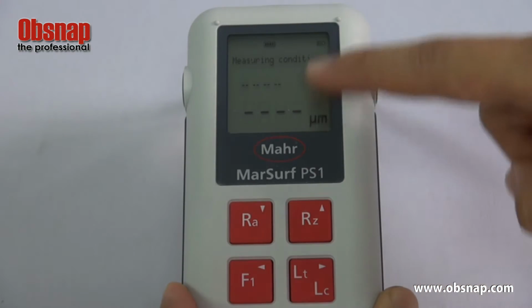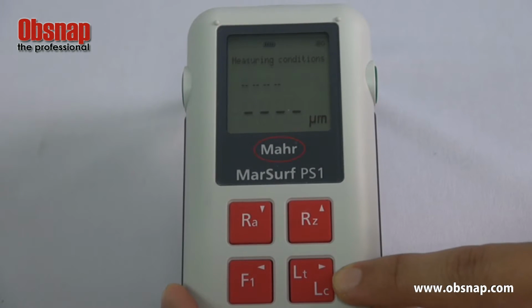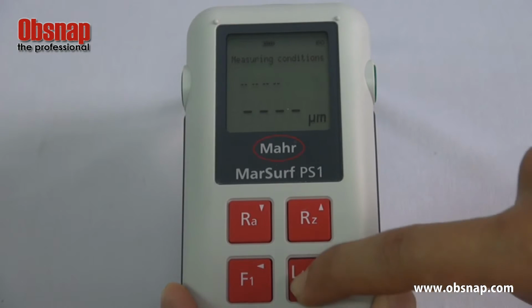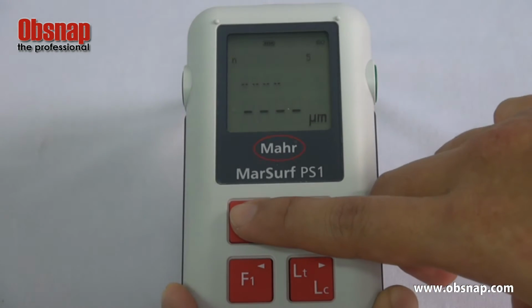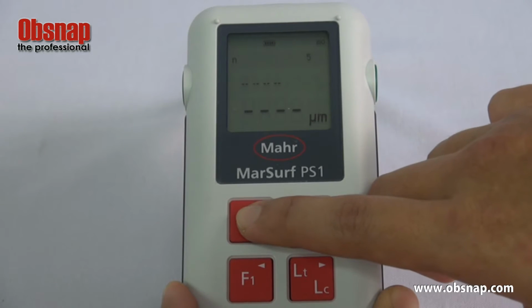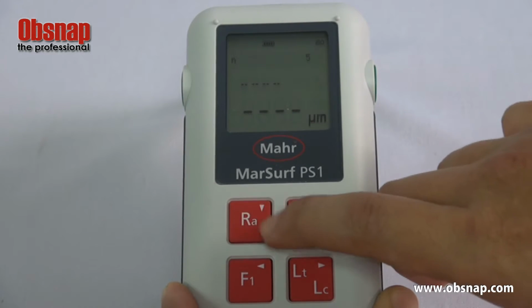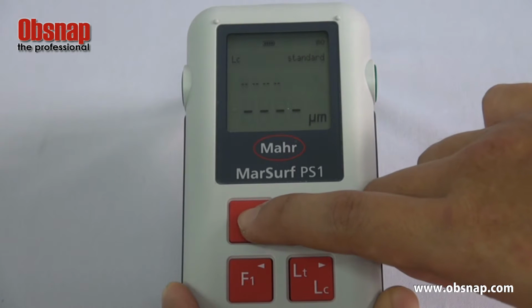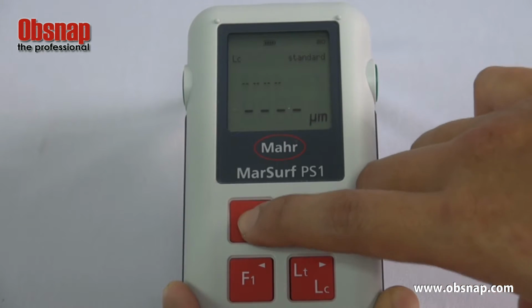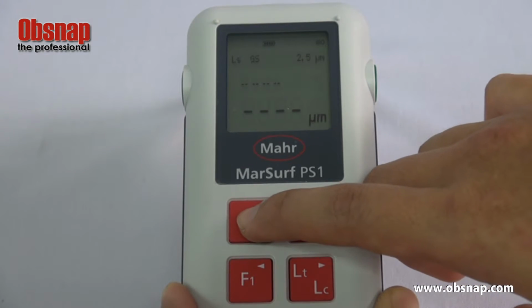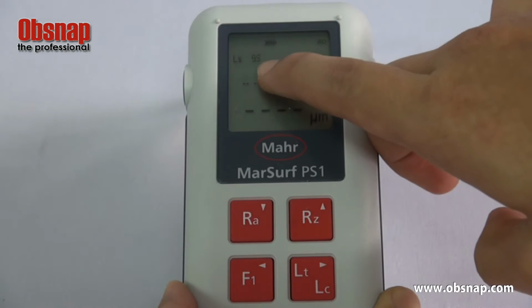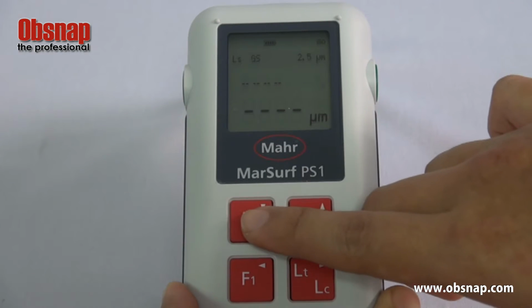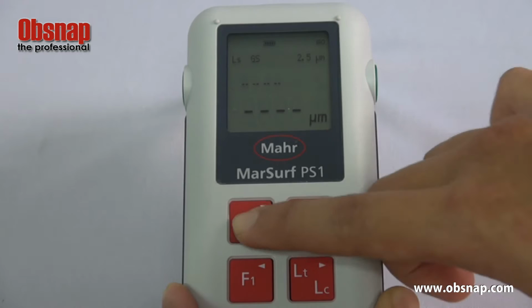To enter into the sub-menu, you just press the LT, LC here with the cursor to the right. Yep, so you can see the first one is N. N is the number of segments. There are 5 segments for this roughness. The next one is LC. Now it's set to the standard. LS, GS, this is the filter. Right now they are using the Gaussian filter, so it's 2.5. You can switch it off as well.